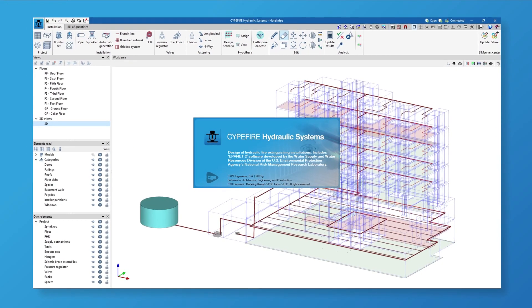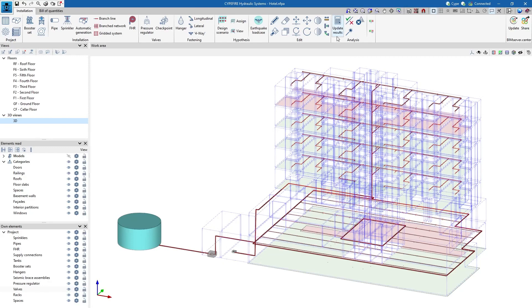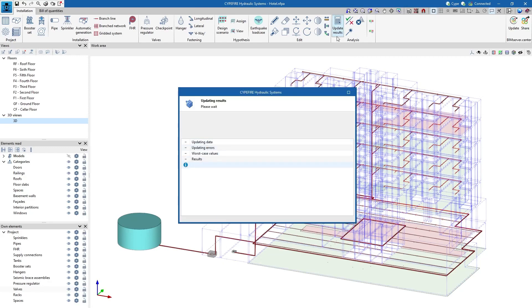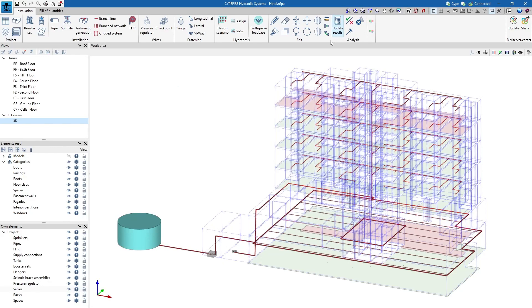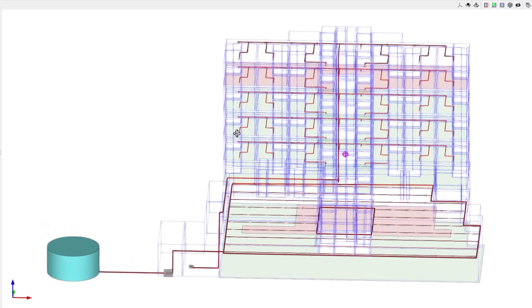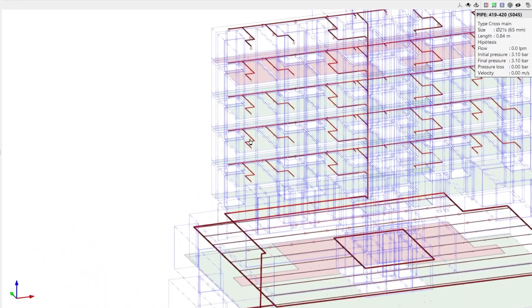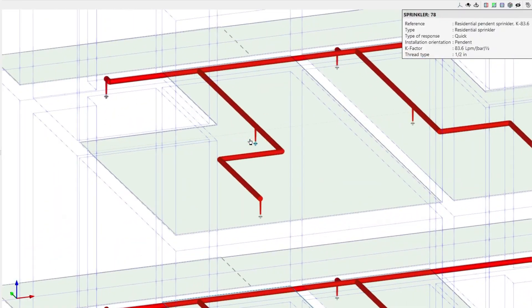The program uses the integrated EPANET 2 analysis engine to carry out the required hydraulic analyses allowing users to select either the Hazen-Williams or the Darcy-Weisbach formulas to calculate the pressure drops. Checks are carried out on all elements according to the code or customized configuration used including geometric and hydraulic analysis checks.